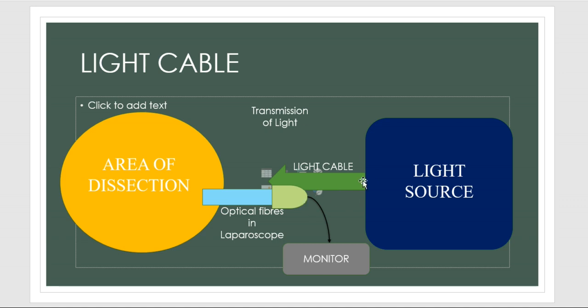From the CCD, the feedback goes to the camera analyzer and then finally to the monitor. So transmission of light in any minimal access surgery occurs through the light cable as well as the optical fibers present inside the laparoscope. The reflected rays come back and are again perceived by the CCD, and then finally the image formed is displayed on the monitor.